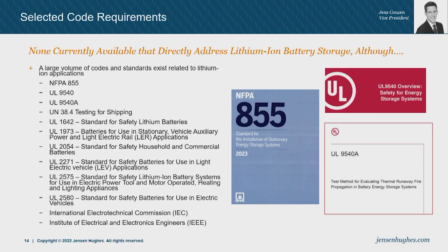So now when we are thinking about storing these cells, we want to make sure that everything is safe, right? And normally, we look at fire safety codes and building codes that tell us what to do. And unfortunately, the codes and standards world has not really caught up yet in addressing that hazard. For example, NFPA 13, which is the code for designing a sprinkler system, tells you do not use that code when you're storing lithium-ion batteries. It does not apply, right? So where do you get the technical basis from? Or where does the authority having jurisdiction, what do they want? What do they deem as safe? So there's a little bit of a gray area.